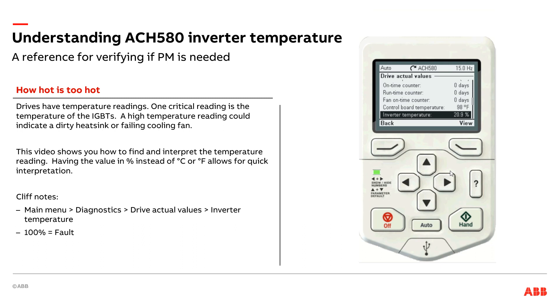So the first thing you're going to see is the temperature is in percentage instead of degrees. Why did we do that? The inverter temperature is the temperature of the IGBTs — insulated gate bipolar transistors. They're the ones that are doing all the work providing the power out to the motor. So do you really know — is 60 degrees Celsius too high on those devices? Is 80 degrees Celsius? Is 110 degrees Celsius? What is too high?